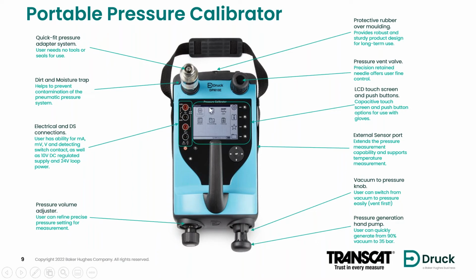Obviously, we have our touchscreen display, which can also be operated through the buttons, ending up at the vent valve here, which you can open up to bleed off pressure to start your calibration, and then obviously close it when you want to start generating pressure. And then again, not visible from the picture here, up at the top we have a gasketed cover for the battery charger connection, as well as a USB port for interconnection with a PC for transfer and exchange of data. So that's all those instruments that I showed on the 2 slides previous, combined into one handy instrument that also has a very ruggedized and convenient handle so that you can grab it quickly to head out into the plant, into the shop, into the field, whatever it is you need to do to go to the site where you're going to be doing your troubleshooting.